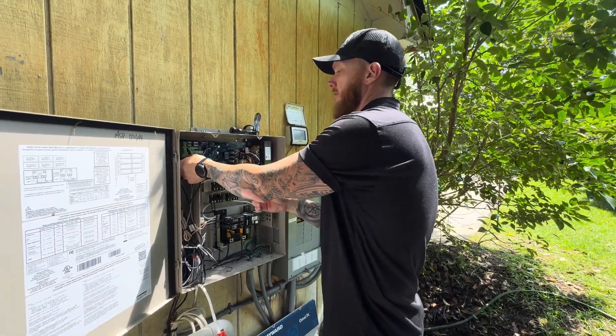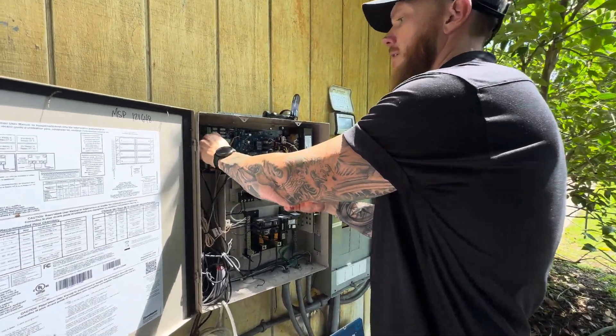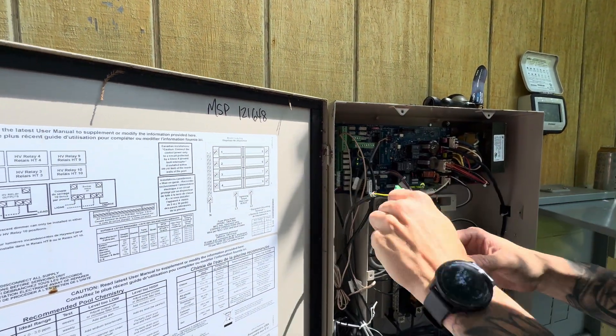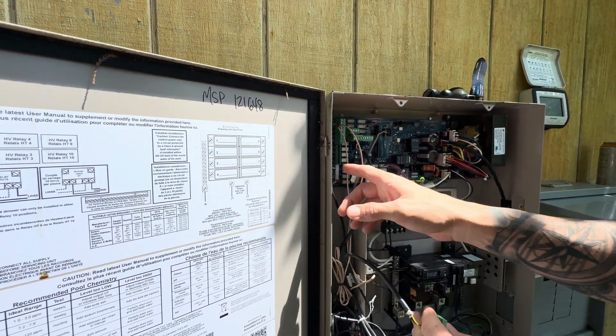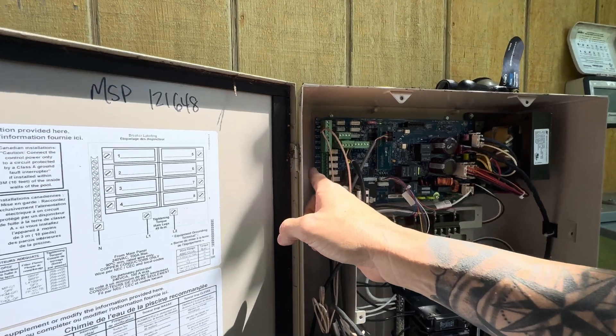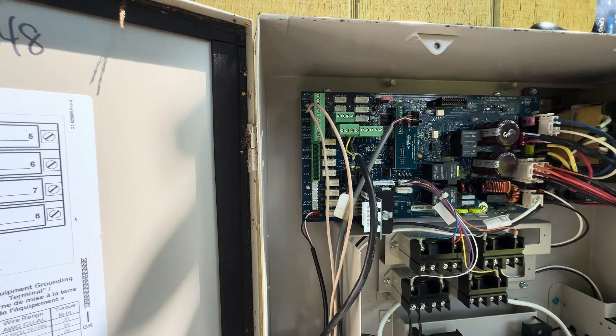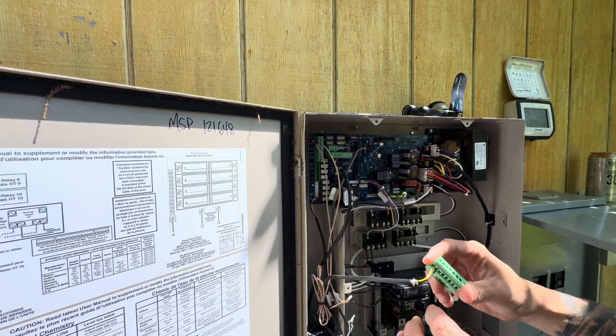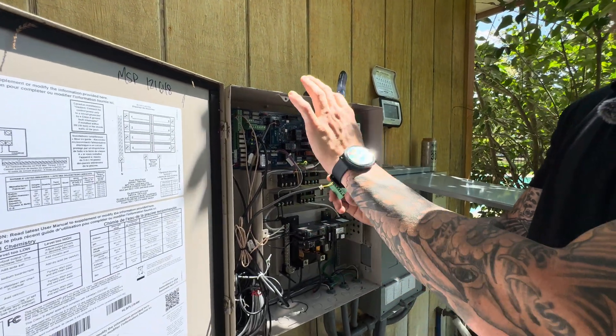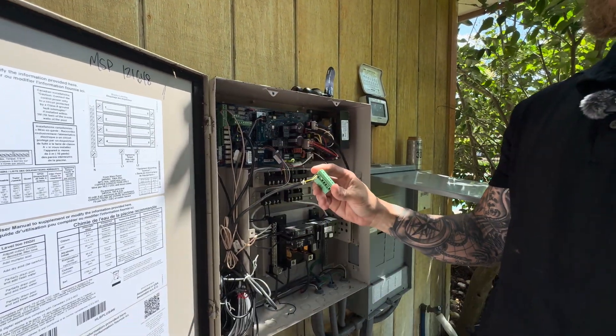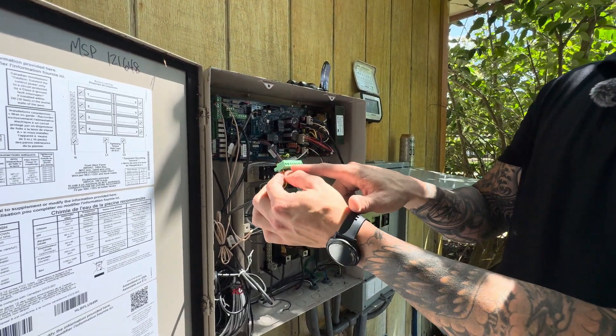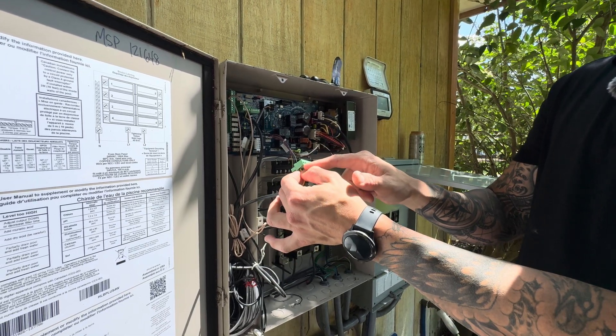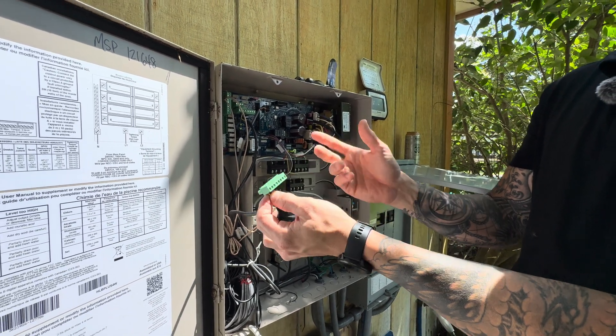We took off our bus that is in control of the heater, as well as low voltage relays 2, 3, and 4. We already went ahead and tightened it, but the issue was a loose data cable running from this control panel to that heater. It was as simple as taking a wire off, stripping it back a little bit, and tightening it down onto this bus. And now we're good.